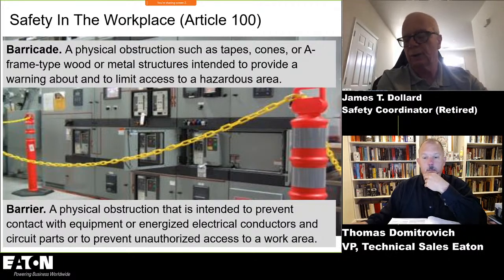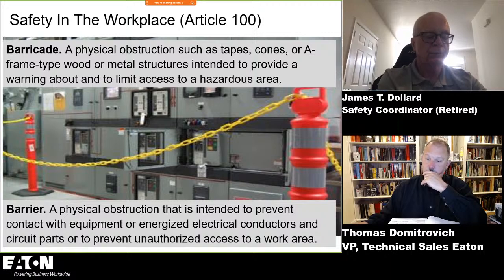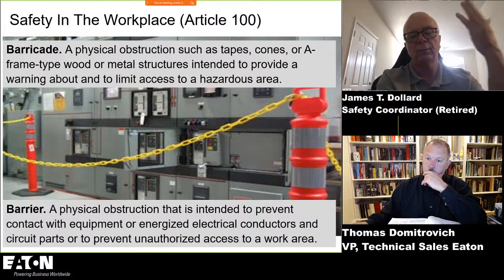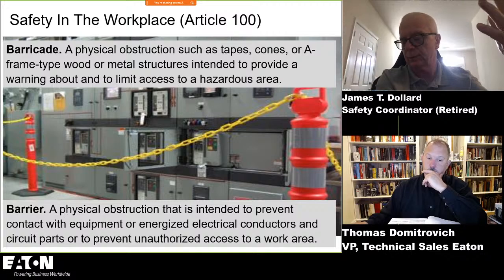And electrical workers aren't going to take a rule and mark 3'6", and then if the arc flash boundary is 2 feet, mark that. They're going to know where that is. What they're going to do is dress outside the furthest boundary, because they intend to get inside the restricted approach boundary. And as long as they're trained properly, they understand that they need those rubber insulating gloves and leather protectors on before they cross the arc flash boundary, because those gloves don't just protect them from shock, they protect them from arc flash. Yeah. Yep.